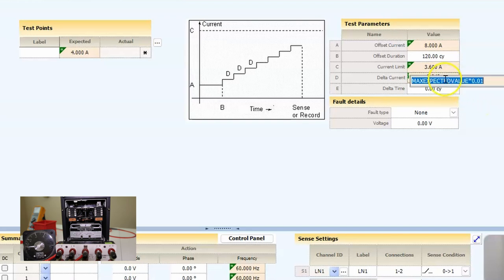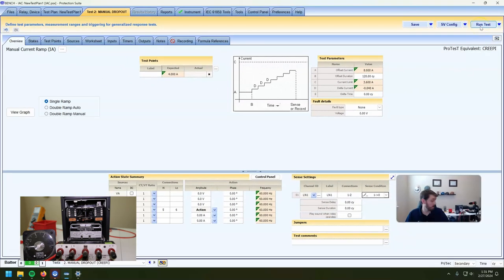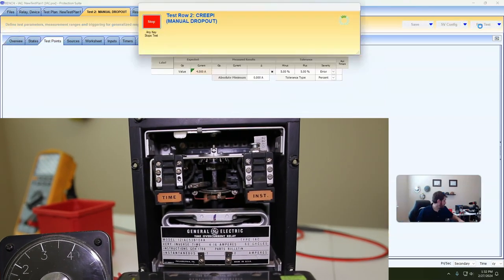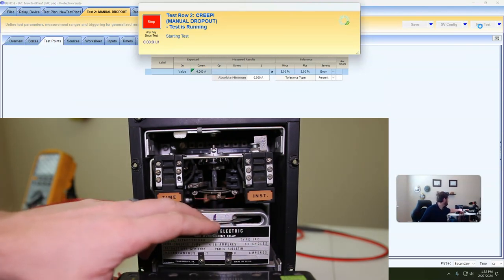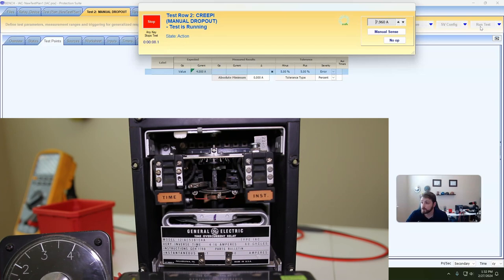The disc has to move a lot less to do that than it does for my eyes to see when the disc actually stops moving. It's just a different way to do it. I'm going to manually hold the disc closed, start the test, and then ramp the current down until it drops out. That's what we're actually going to record. The contact is currently closed and I'm going to ramp down until that contact opens — it's going to clock the actual amount of current at which the trip contact stops being closed.